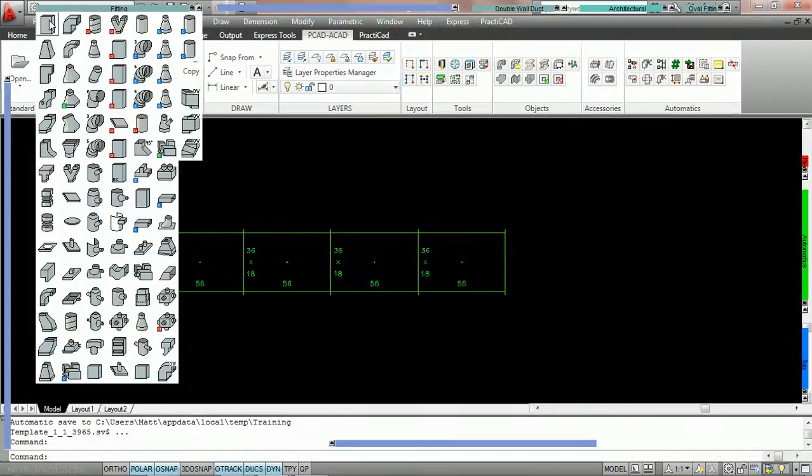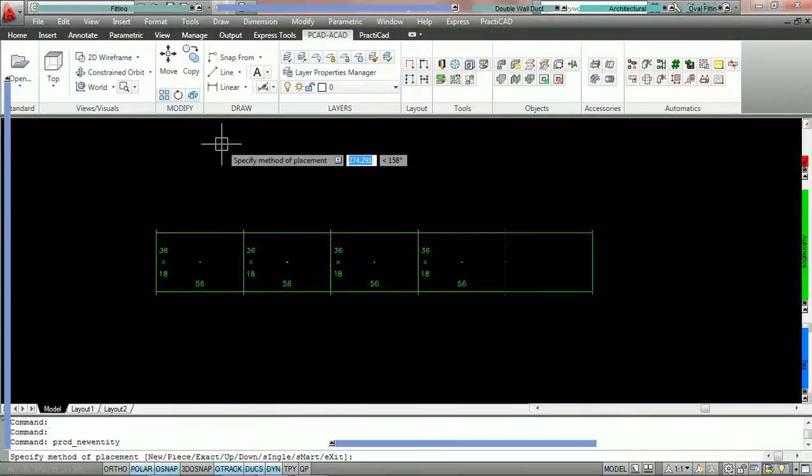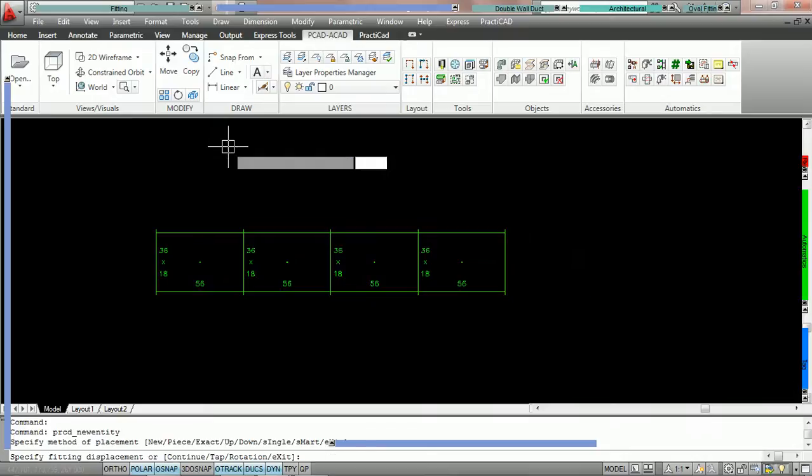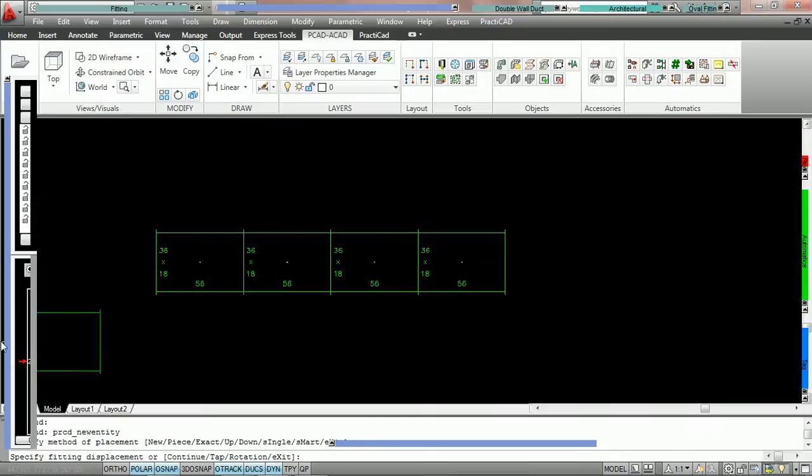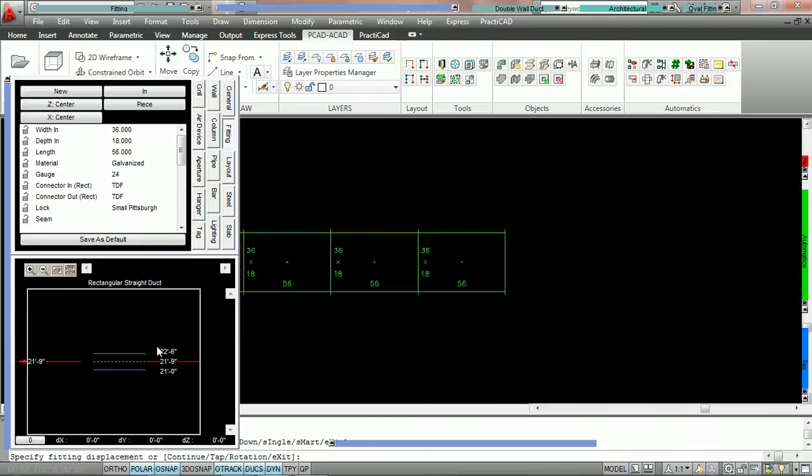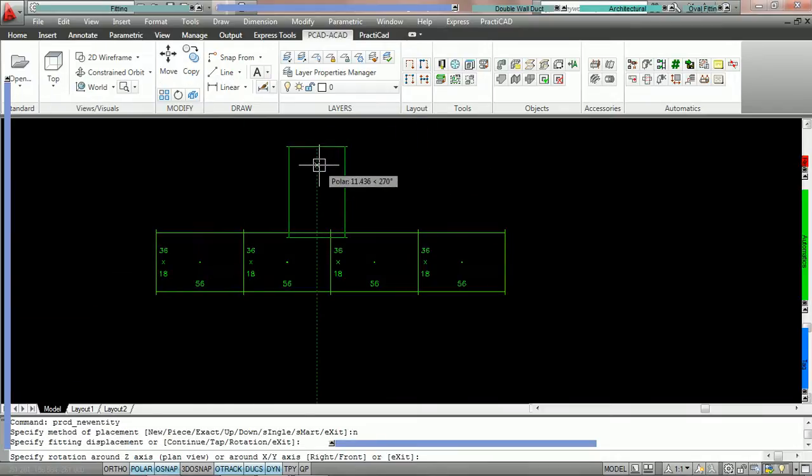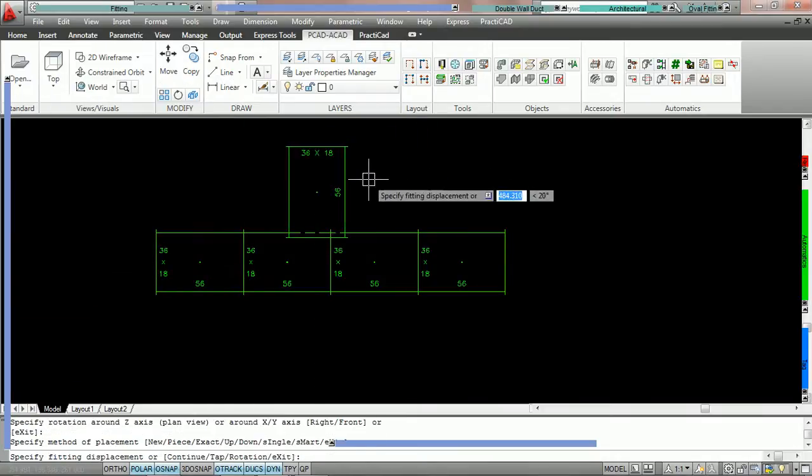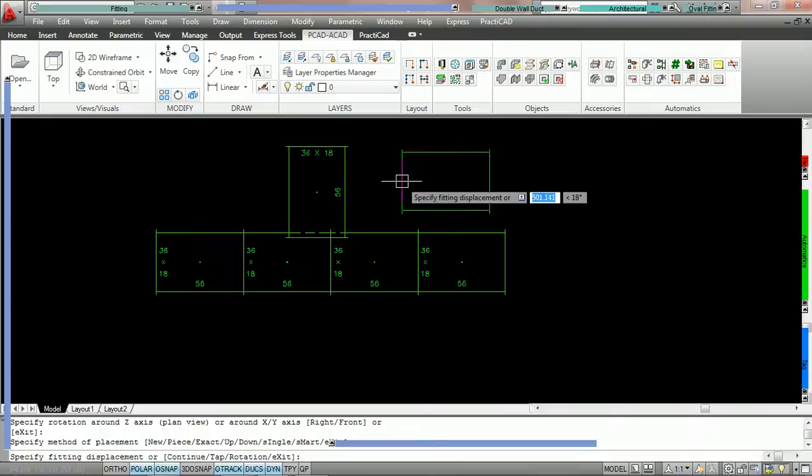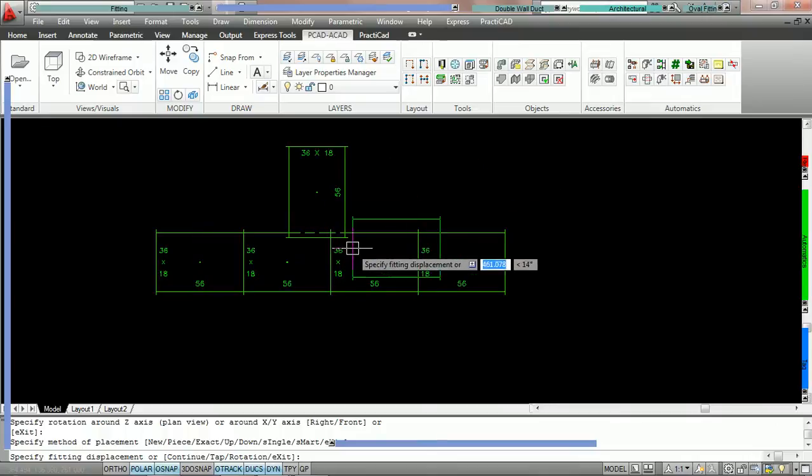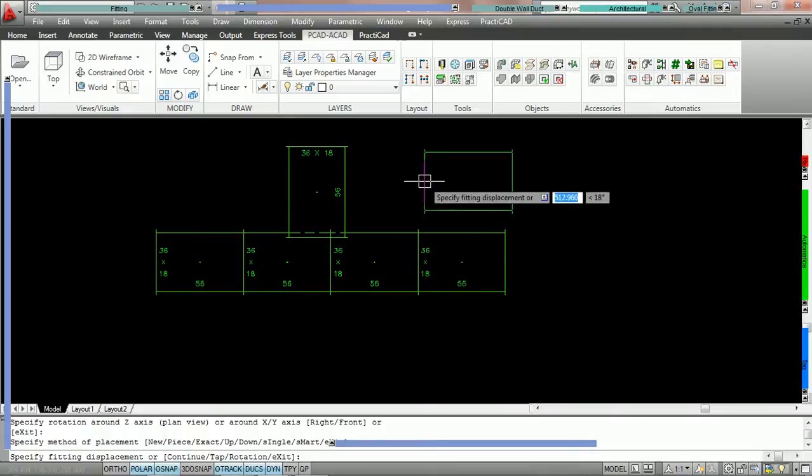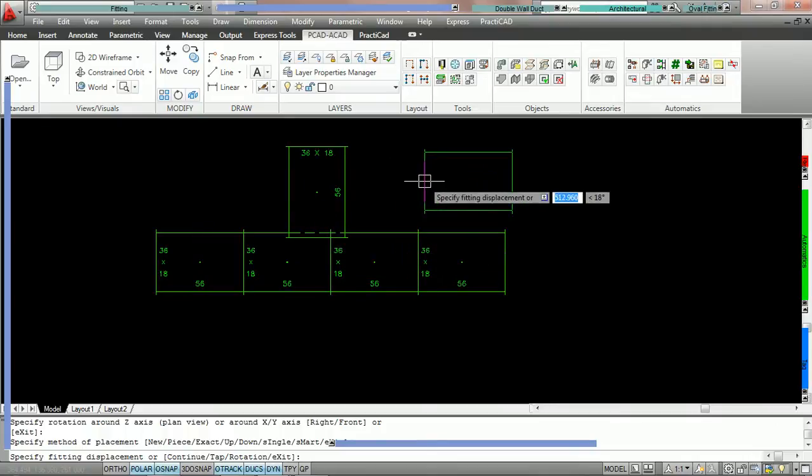Now we're going to grab a fitting. We're simply going to put it at an elevation higher than the duct on the drawing. So we're going to say bottom at 21 foot. Now we're going to simply place one fitting on the drawing. Once we click to place the fitting here, you can see that PractiCAD is already generating the hidden lines.